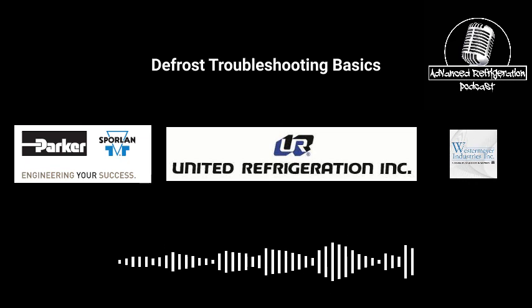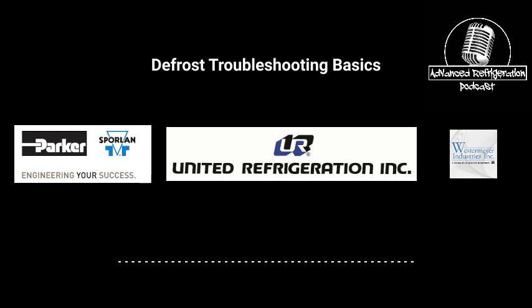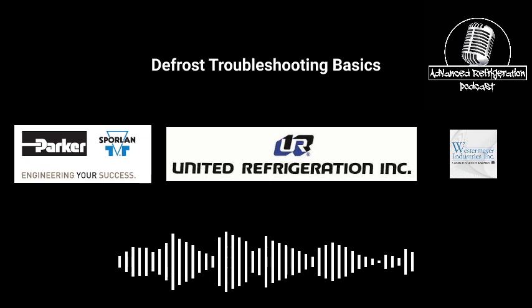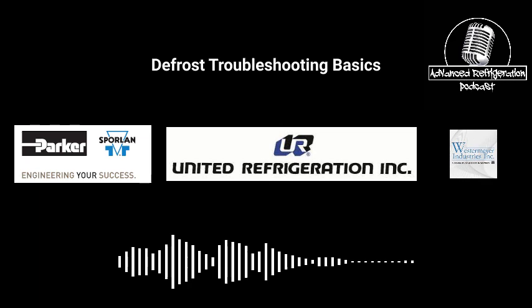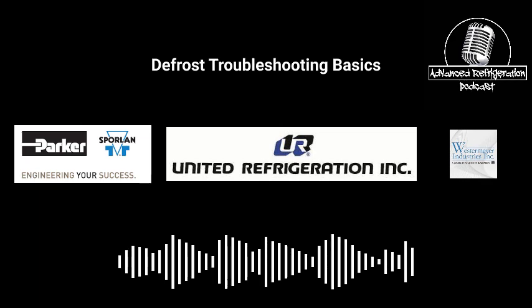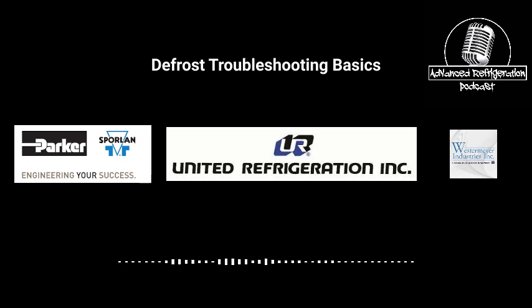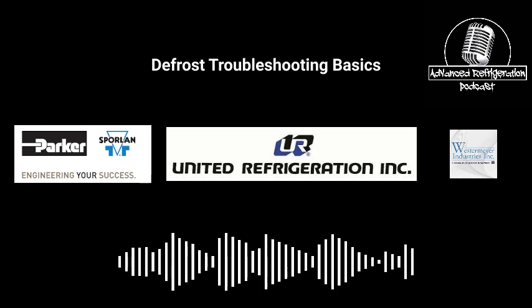So typically it's a defrost termination issue when you have this erratic high liquid level. We get them all the time on some of the bullseyes. One of the things that we saw is that you can have it because the defrost termination sensor is not accurate, where it's reading higher than what it is. So that's one thing. The other thing that could be causing that is the defrost termination temperature.